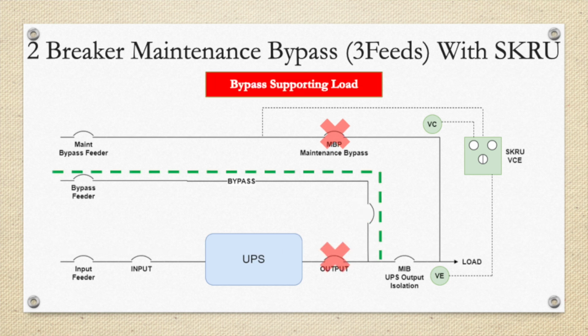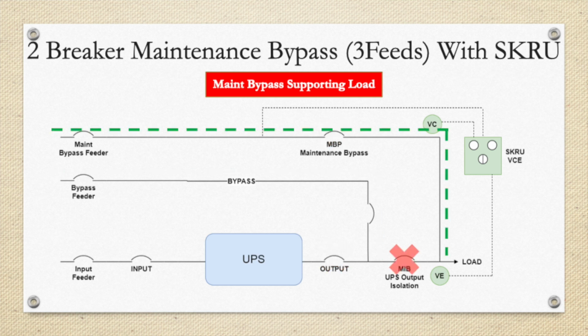The next drawing shows we've just transferred the unit to internal bypass, which will now enable the SKRU unit. And then the final drawing is showing us successfully running on maintenance bypass and having total isolation capabilities and load testing capabilities of that UPS while still maintaining the load on the maintenance bypass.